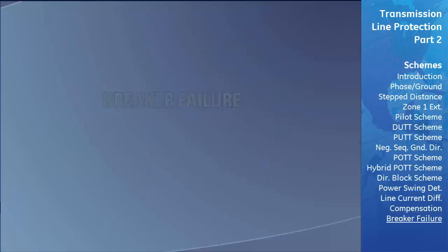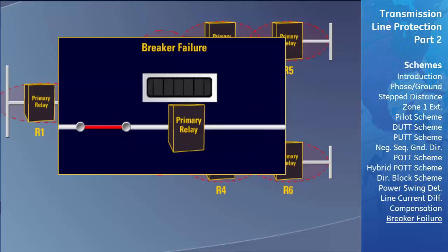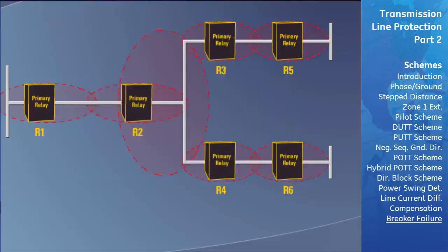Let's look at an example of a breaker failure protective element. In this example, the protective relays operate correctly, but the associated circuit breaker fails to clear the fault due to some malfunction within the breaker or its control circuits. The fault remains on the system until some other means is used to clear it. The primary or backup relays start a timer once a fault is detected. The timer then times out and sends a trip signal to all breakers that can feed the failed breaker with power.